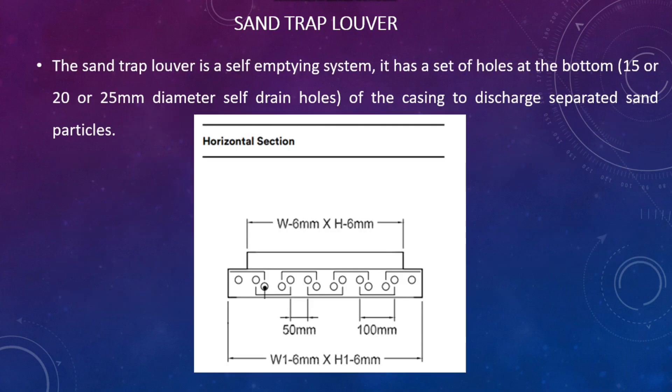The sand trap louver is a self-emptying system. It has sets of holes at the bottom of the casing — 15mm, 20mm, or 25mm diameter self-draining holes — to discharge separated sand particles.